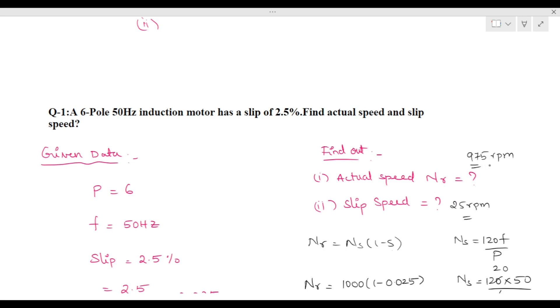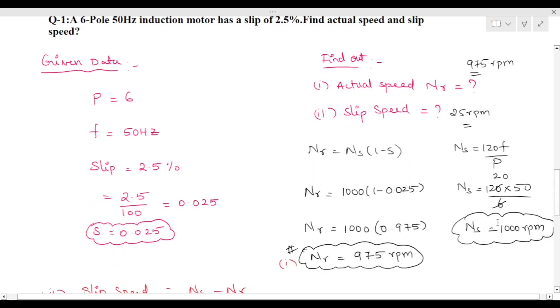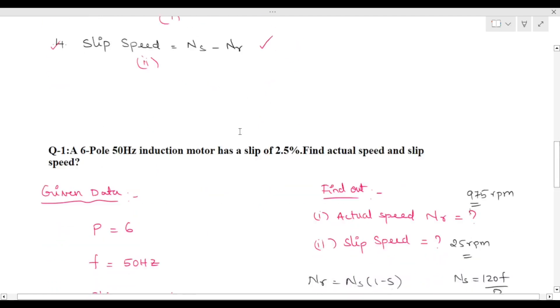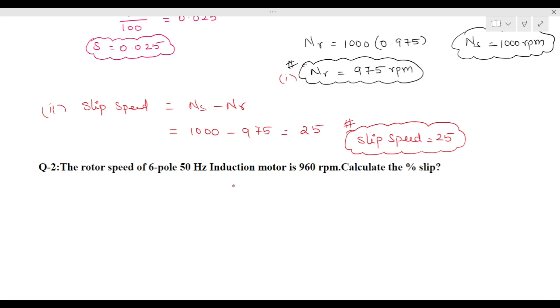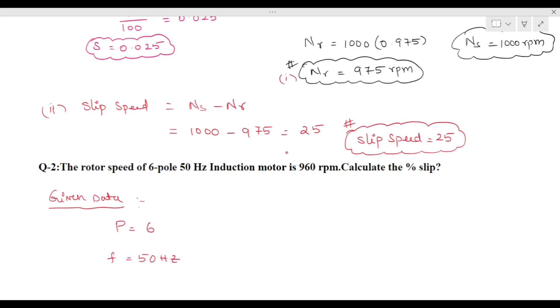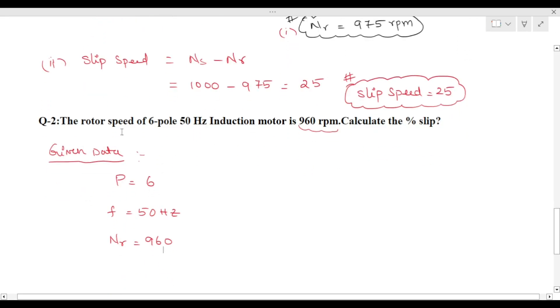Both values have been found: actual rotor speed is approximately 975 rpm and slip speed is 25 rpm. These formulas were used as stated above. Now coming to the second problem: the rotor speed of a six-pole, 50 Hz induction motor is 960 rpm. Calculate the percentage slip.